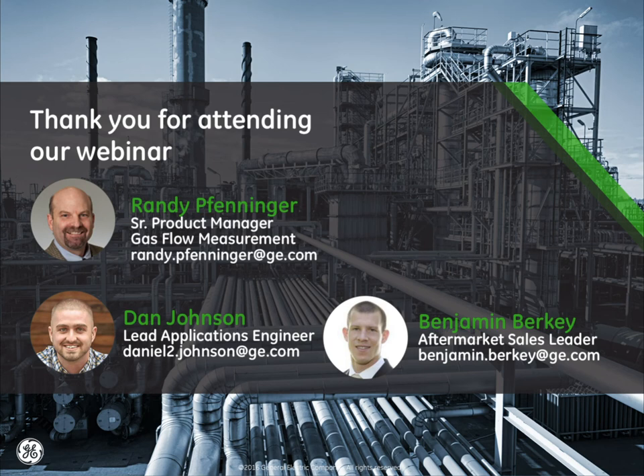Thanks, Randy. So Flare IQ is a new product that GE has launched this year to help our customers with a total solution approach to the refinery sector rule. Flare IQ is a software package that is a plug-in to the DCS. It's not a controller, it's not a PLC, and it takes in all of the data that can be collected from ultrasonic meters that are deployed on the flare line and all assist flows, and provides the refinery with proper provisional set points of steam and fuel.